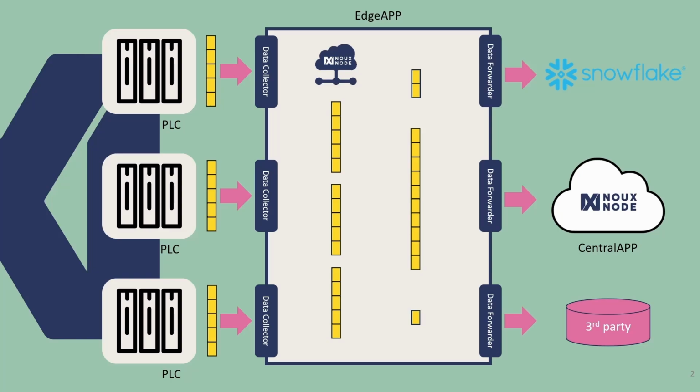And other benefits include that we can, of course, now mix these technologies a bit, meaning, for example, that we can collect data from a Modbus system and then forward it as OPC UA. And then we can set multiple destinations for what we actually use. Ultimately, we can even drop our central application from this, so we don't take the data, but it's only used to configure the edge and send to the correct destinations.